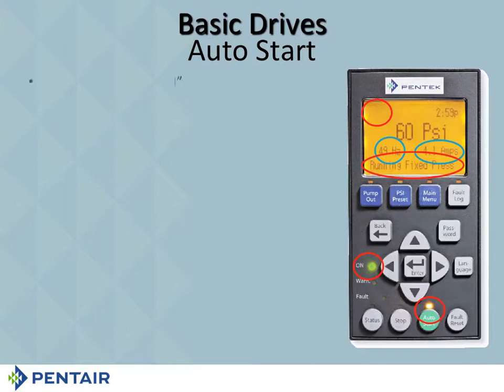Okay? It indicates auto line fill first. Where it says running fixed pressure, it's going to say auto line fill first. Now that may disappear very quickly. You may just see it flash, and if you're not watching, you may not even see it at all. Because if your line already has 10 psi in it, it just goes right to 60 psi then. Okay? But if you're filling the line up for the very first time, and you've got a long line to fill up, it will say auto line fill.